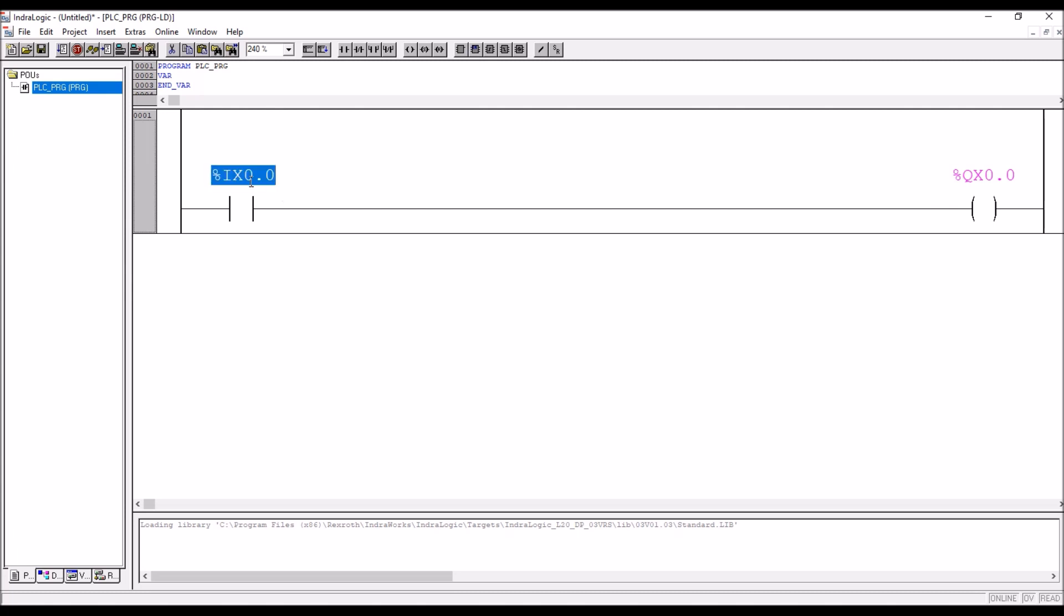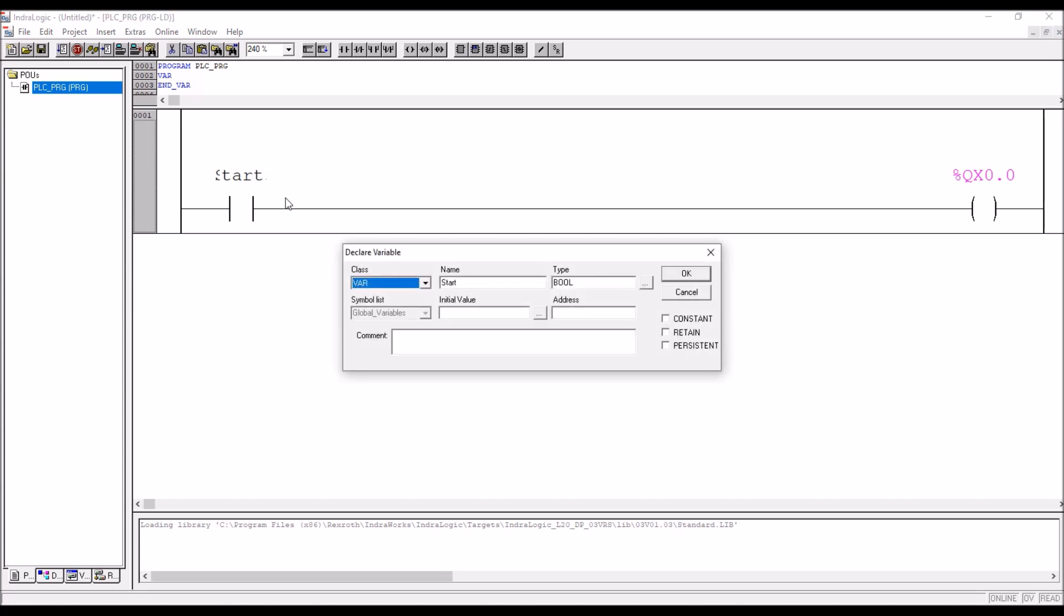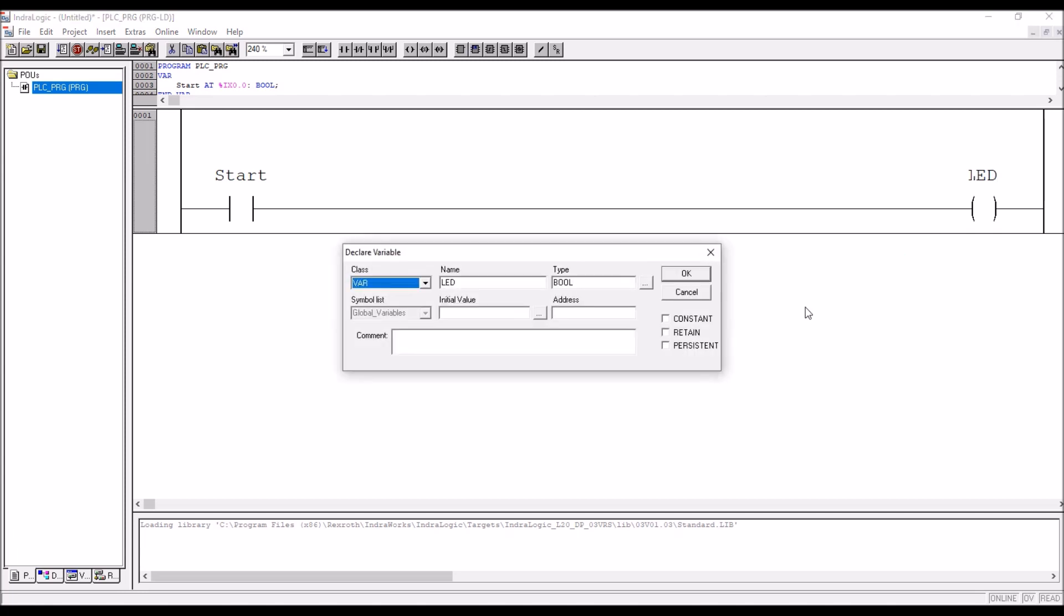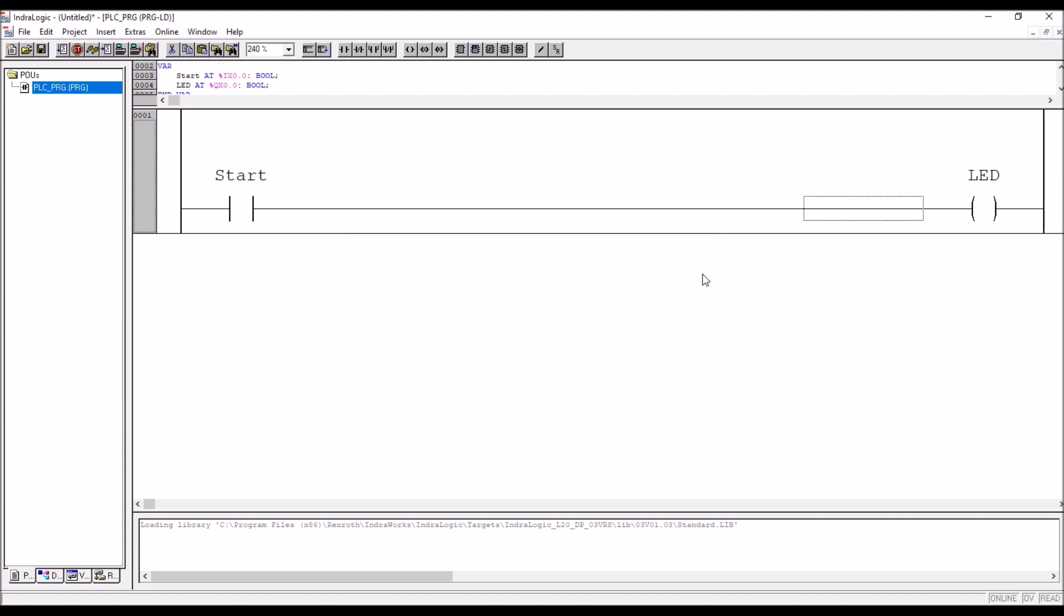You can type, say for example I am using start push button. I am connecting start push button to the first input, so first input address is percentage IX0.0. Then I have got one LED, so LED I am wiring up to first output, so first digital output that is percentage QX0.0. This is how you can address the input and output.